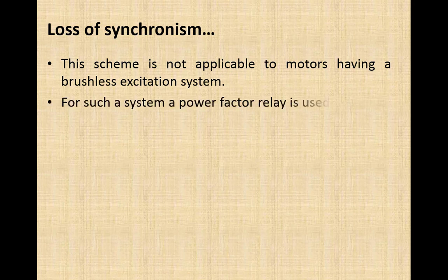And then the alternate is the power factor relay, because in case of normal operation, synchronous motors are operated in overexcited condition, meaning they are absorbing real power and providing reactive power to the system. And in case of loss of synchronism, it will start absorbing real power as well as reactive power. So its power factor will change from leading to lagging. So this lagging power factor is an indication of loss of excitation or poor excitation.